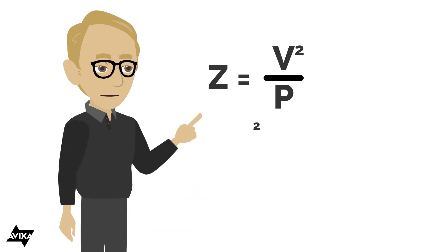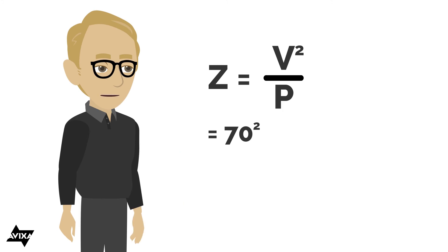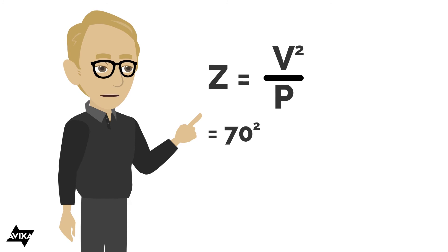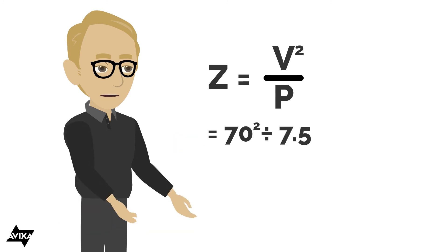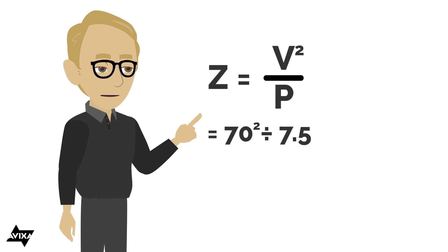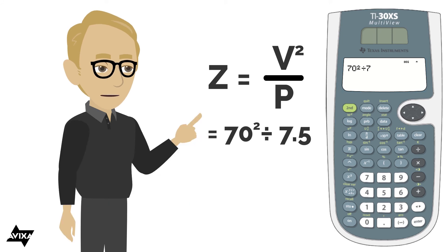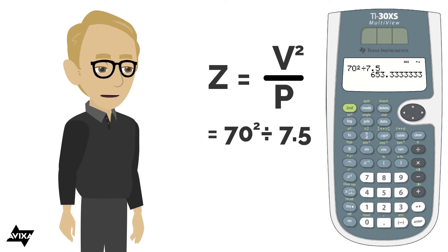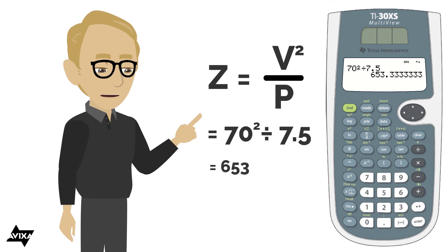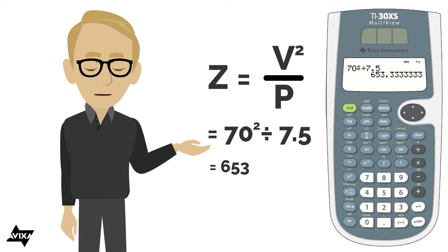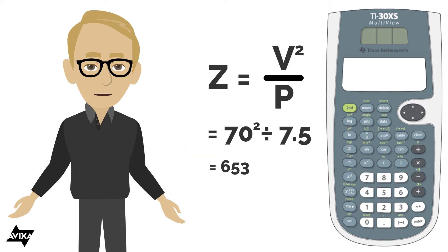Let's say we're working with a 70-volt system — so our voltage is 70 squared. If it were a 100-volt system, it would be 100 squared. And let's say we're tapping a loudspeaker at 7.5 watts. So 70 squared divided by 7.5 — for an individual loudspeaker — gives us about 653 ohms of impedance. Again, this gets us in the ballpark, not exact. But now I can measure the loudspeaker with an impedance meter and verify what I've predicted.